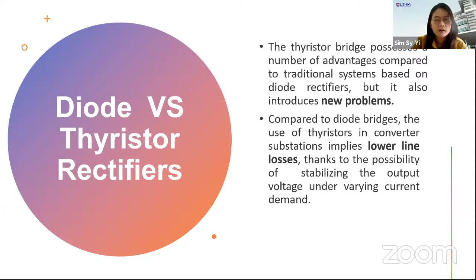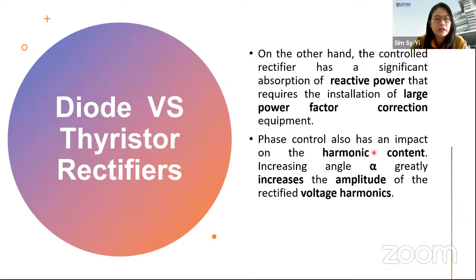But we have to notice that the thyristor has significant absorption of reactive power. So if we are using the thyristor, we have to know about power factor correction - we need to install power factor equipment. Also, they will come up with some harmonic content and increase the amplitude of the voltage harmonics.